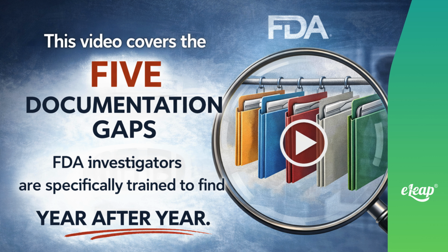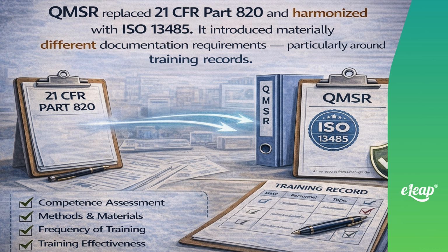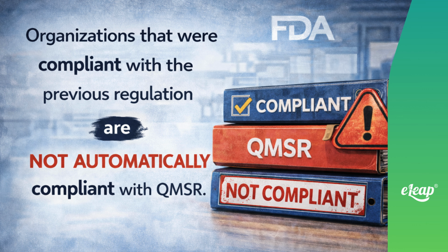This video covers the 5 documentation gaps FDA investigators are specifically trained to find. The QMSR replaced 21 CFR Part 820 and harmonized with ISO 13485 2016. It introduced materially different documentation requirements, particularly around training records. Organizations that were compliant with the previous regulation are not automatically compliant with QMSR.